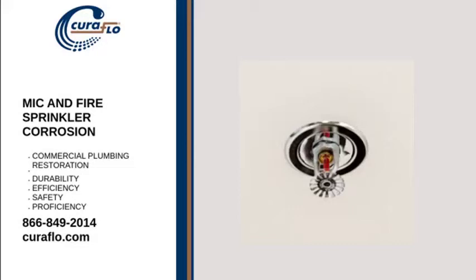MIC and copper pipe corrosion are also problems in other mechanical systems in related fields, including gas pipelines and cooling towers. Those mechanical systems are however mostly dynamic and have relatively constant flow rates. Fire protection systems don't have these constant flow rates, and there are also various differences when fire protection systems are drained and refilled. The fire protection community faces unique MIC challenges, while it also provides ever-evolving solutions to eliminate systems failing prematurely.